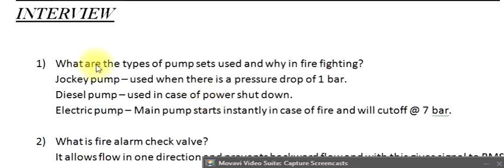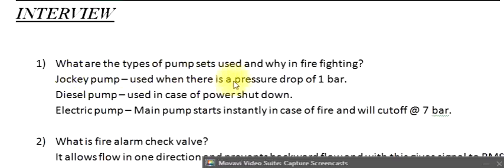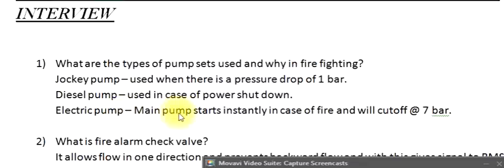Question 1: What are the types of pump sets used and why in firefighting? Jockey pump is used when there is a pressure drop of 1 bar. Diesel pump is used in case of power shutdown. Electric pump (main pump) starts instantly in case of fire and will cut off at 7 bar.